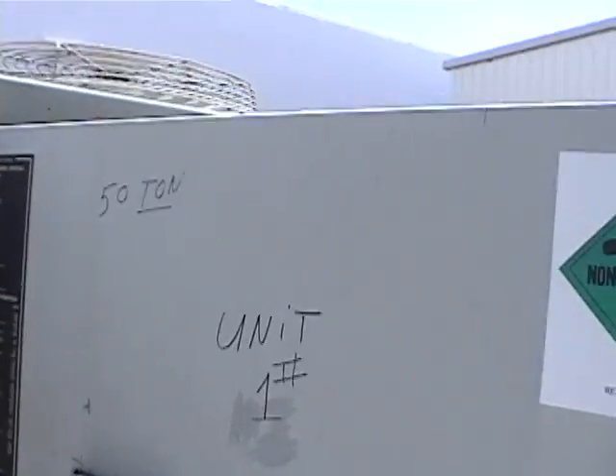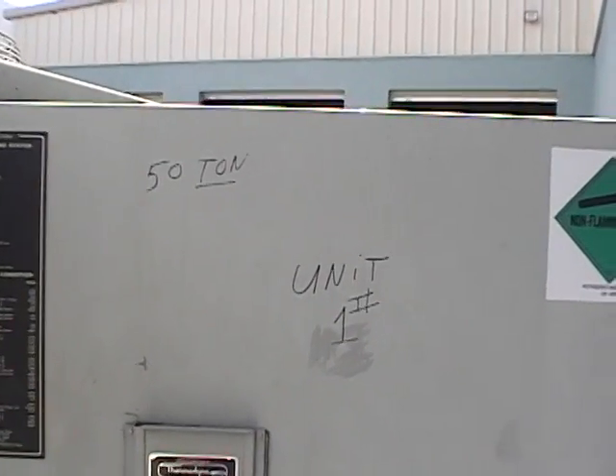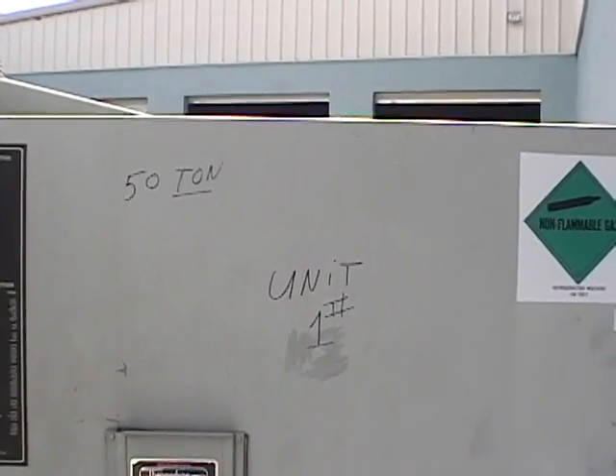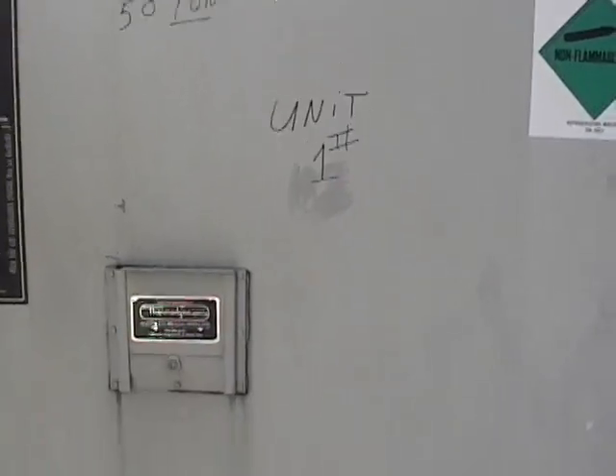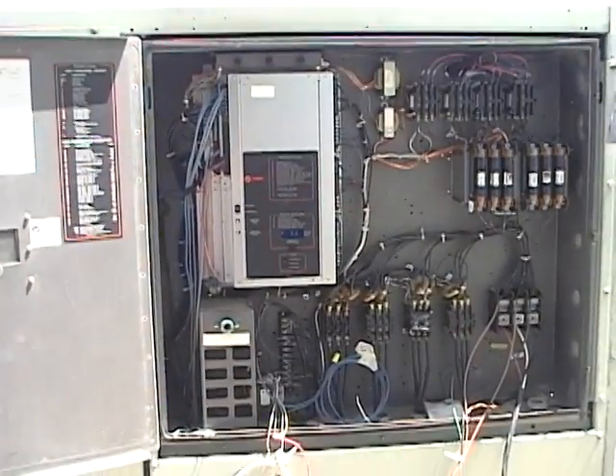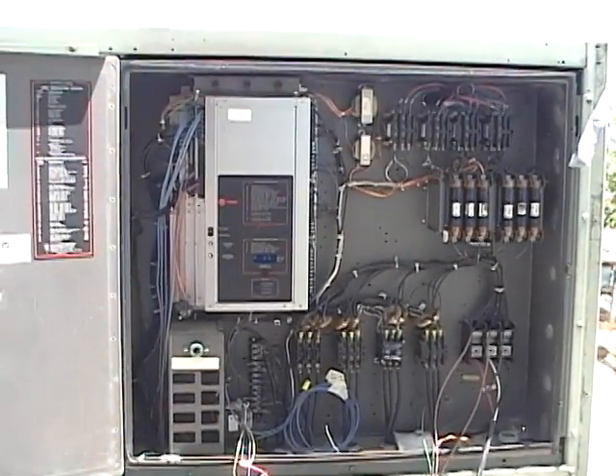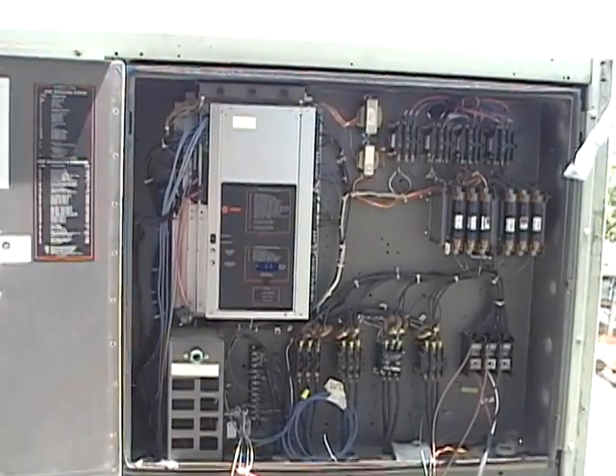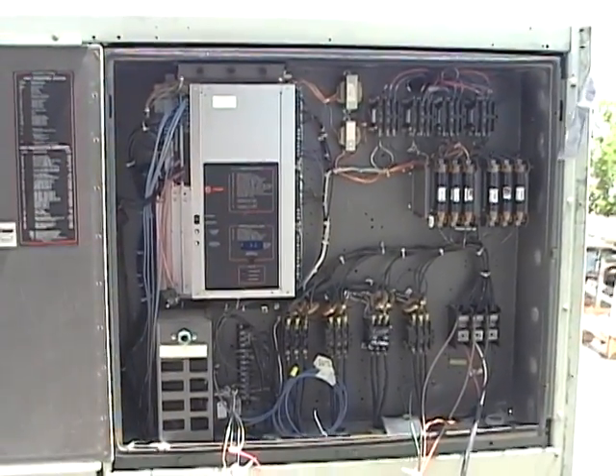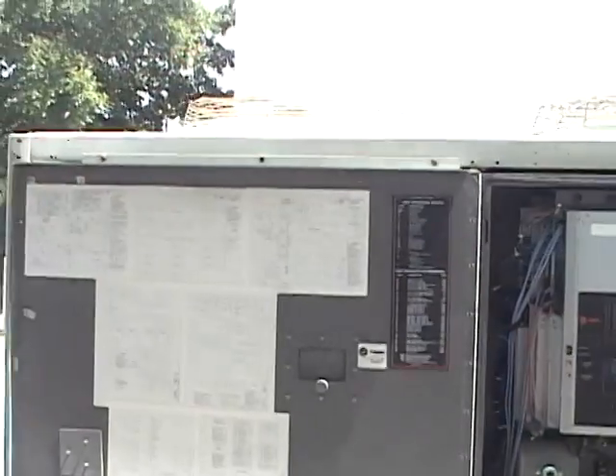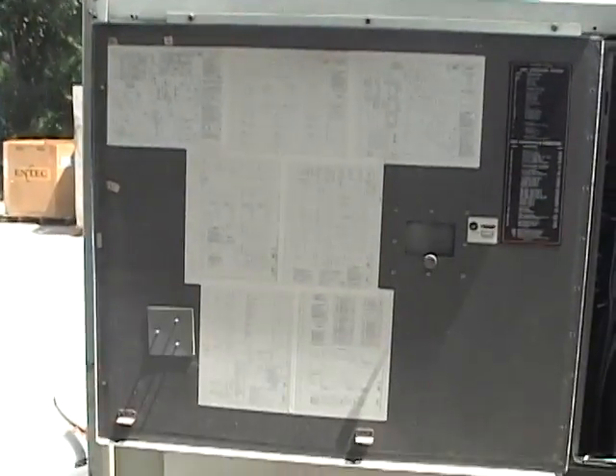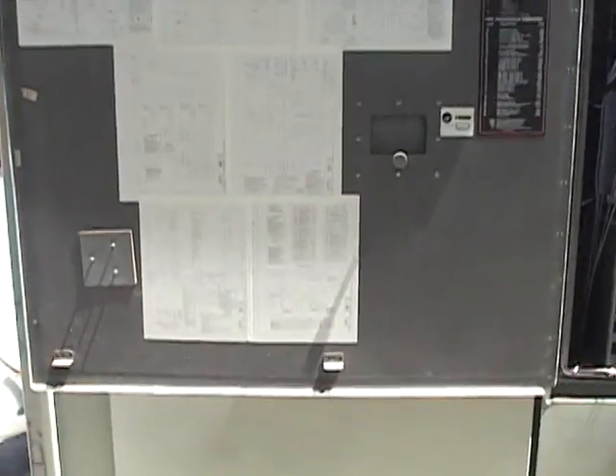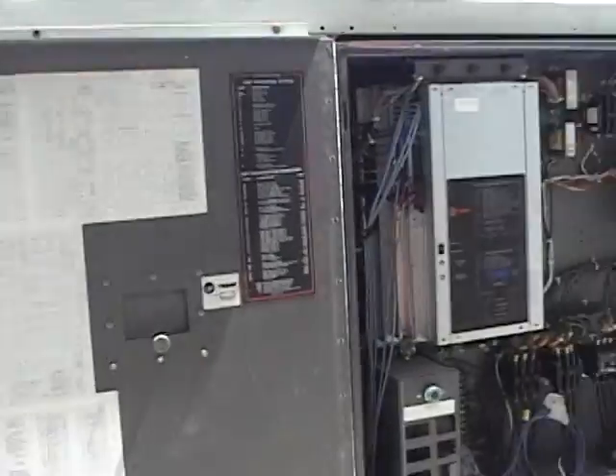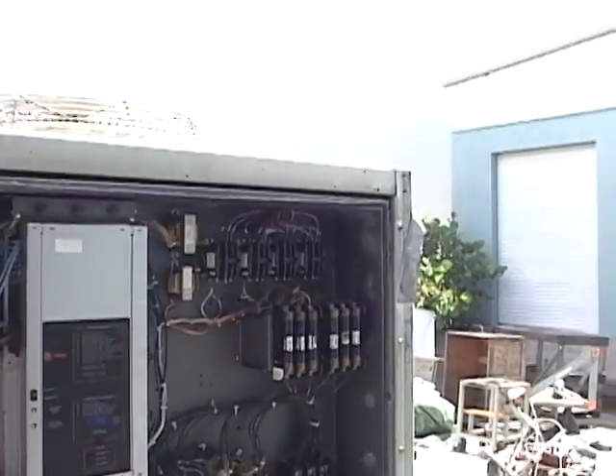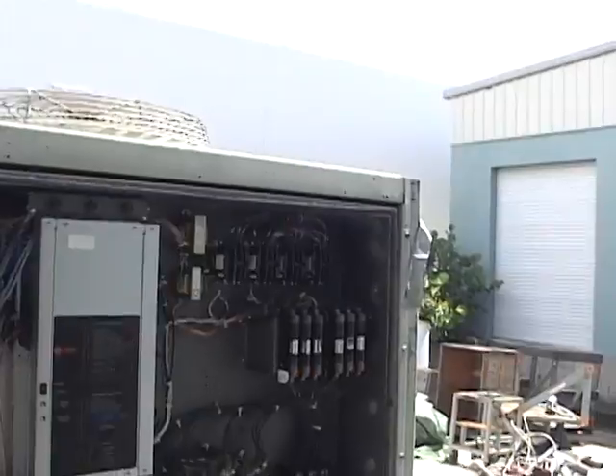This unit is Unit 1. We have 2 of these units. This is Unit 1. This is an R22 unit, and she has now reached 55, so she will now shut off her compressors. Okay, so this is an R22 unit. You'll notice everything on the door is complete, very, very legible. No problem reading any of the wiring. Nothing inside has really been changed. It's pretty much the way it belongs.